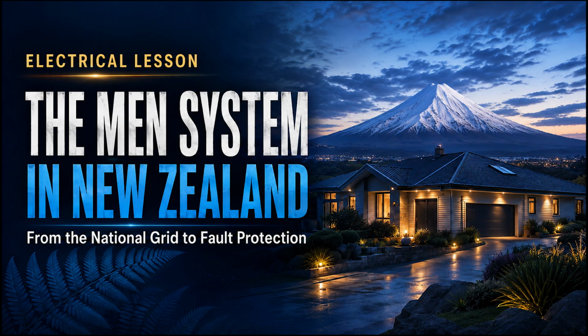If a second Earth fault develops on another line, a dangerous line-to-line fault path can be created through the earthing system. In the New Zealand public low-voltage distribution system, the neutral is deliberately connected to Earth. This fixes the neutral point close to Earth potential and gives predictable line-to-Earth voltages.